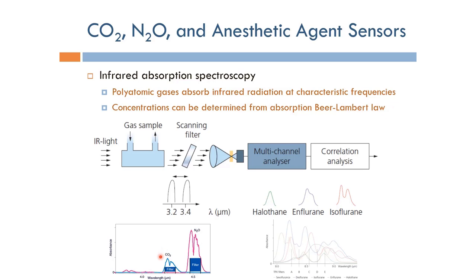For example, if you look at CO2 or carbon dioxide versus nitrous oxide, we find that each of them has a different bandwidth or a different wavelength where their absorption is present. So basically, if we use a filter, we can extract this part here to measure the nitrous oxide, and use another filter to measure this part here to measure the carbon dioxide in the breathing gas.